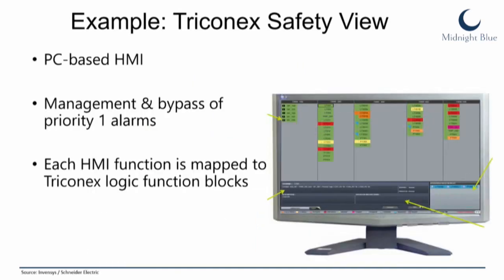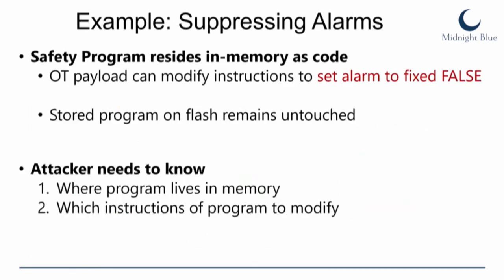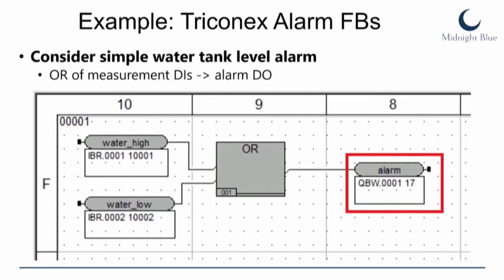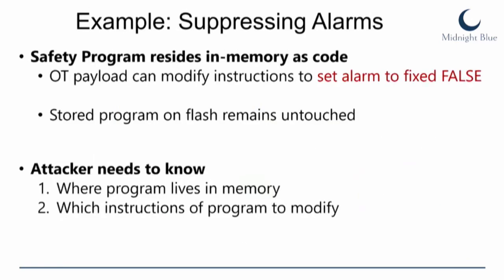For TriConex, you have Safety View, which is a PC-based HMI solution. It allows for management and bypasses of all these alarms, and each HMI function is mapped to a TriConex logic function block. That looks something like this — for example, a water tank level alarm, with a water-high and a water-low signal, and an OR of them raises an alarm.